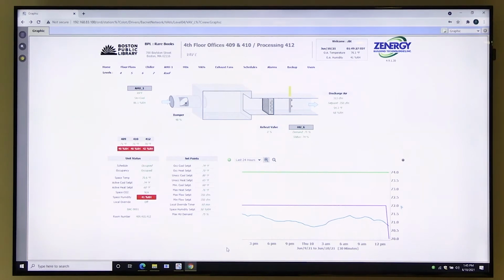What that typically means is a power issue. If it's not a power issue, maybe there's a contractor, an electrician, messing with wires and wires got cut. Maybe a mechanical contractor was servicing equipment and pulled wires off, who knows. Basically, if yellow or orange is seen on just one controller, say just this VAV is yellow or orange, we're having a communication issue with that box.